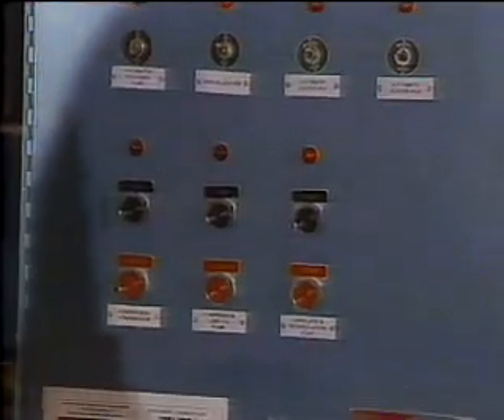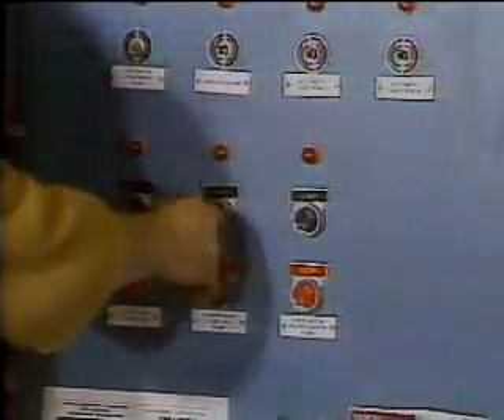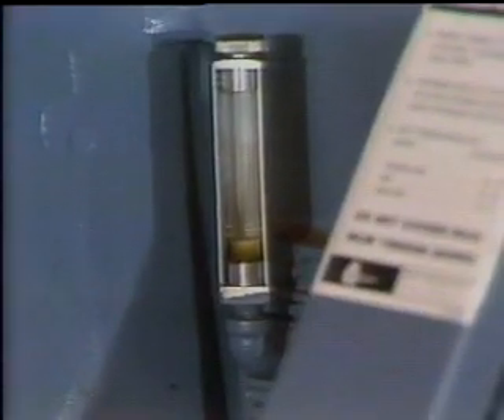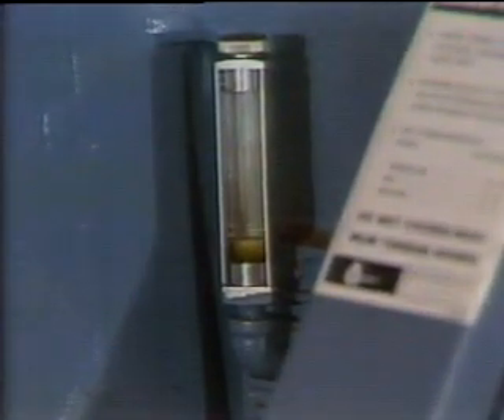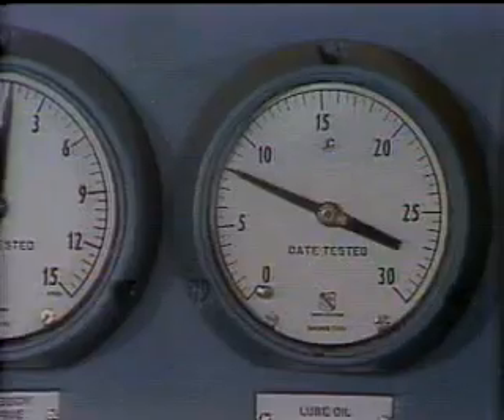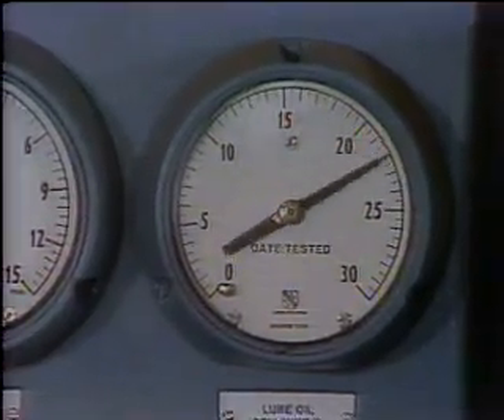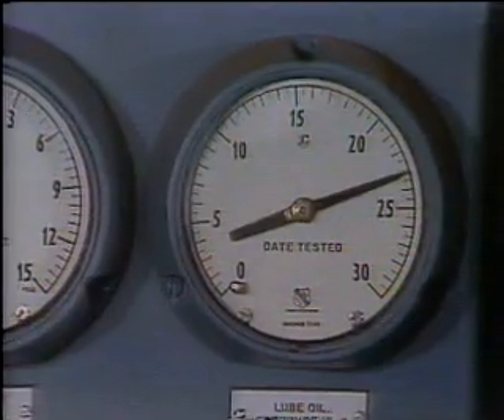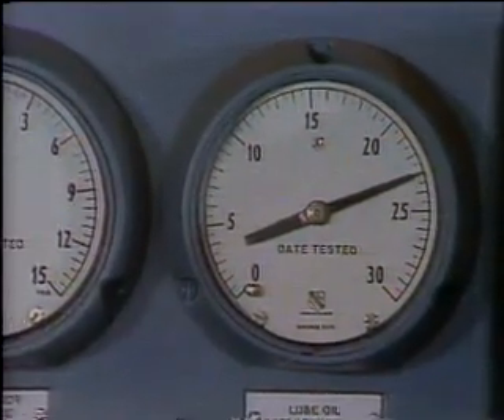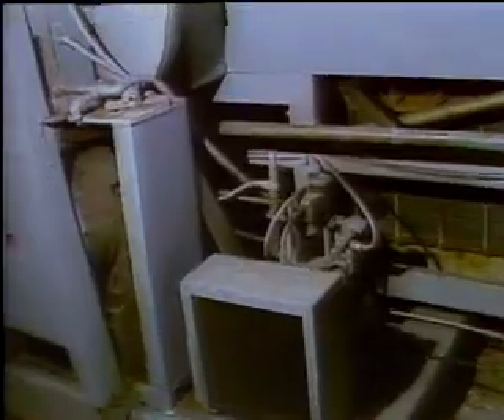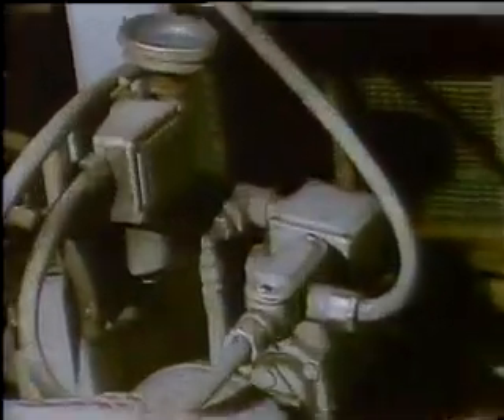2 minutes before starting the centrifugal compressor, turn the lube oil pump on. This will get plenty of oil flowing through the compressor and get all of the air out of the bearing cavity. Watch the oil pressure. Make sure that it's between 15 and 20 pounds per square inch before starting the centrifugal compressor. It might be necessary to readjust the oil bypass valve to get it within this range.